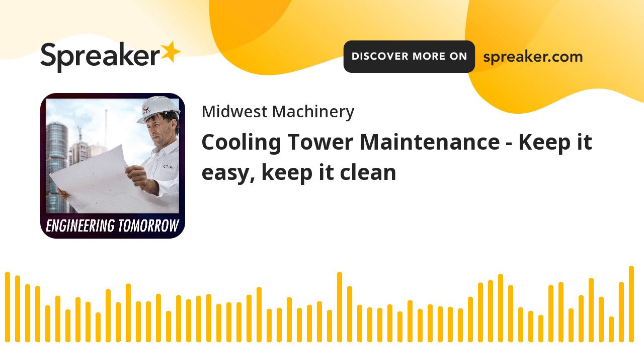I would assume if you don't do that, you're going to have significantly less life on that tower, and I guess it's going to rust. Yeah, it will basically wipe off your galvanization coating, and then there's nothing there to protect the tower, and the water will eat away really quickly. You're going to start to notice leaks very, very soon. It's definitely not something you want to do.